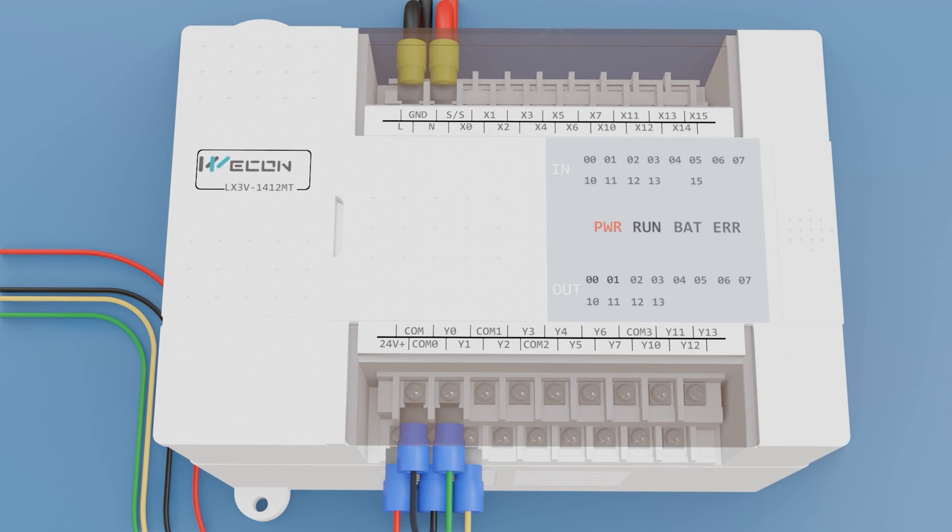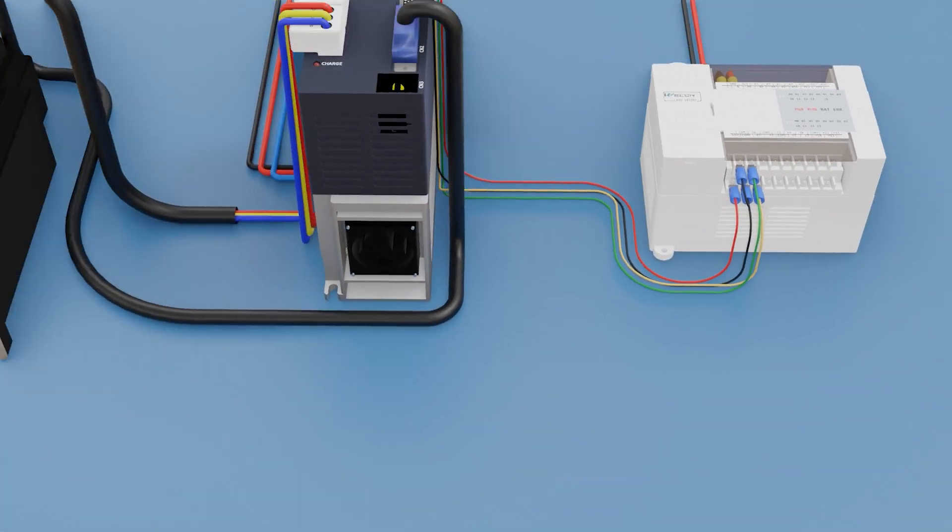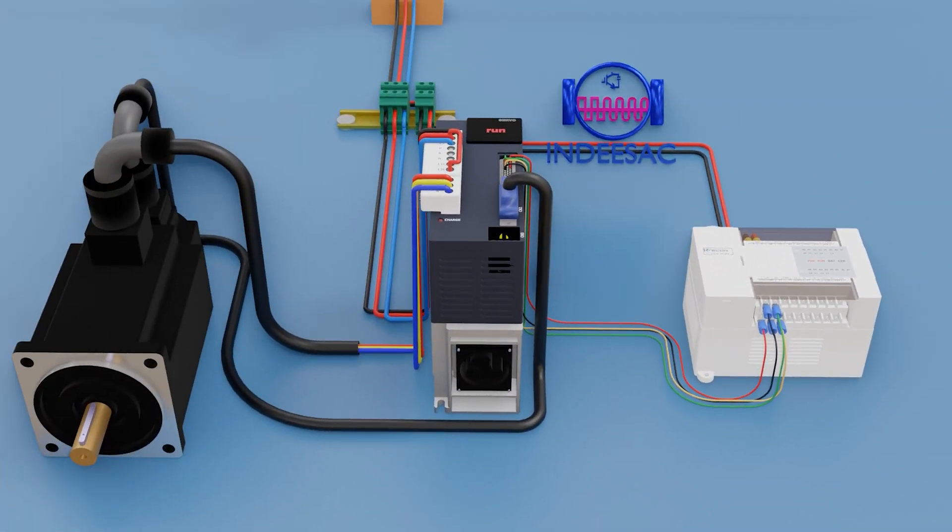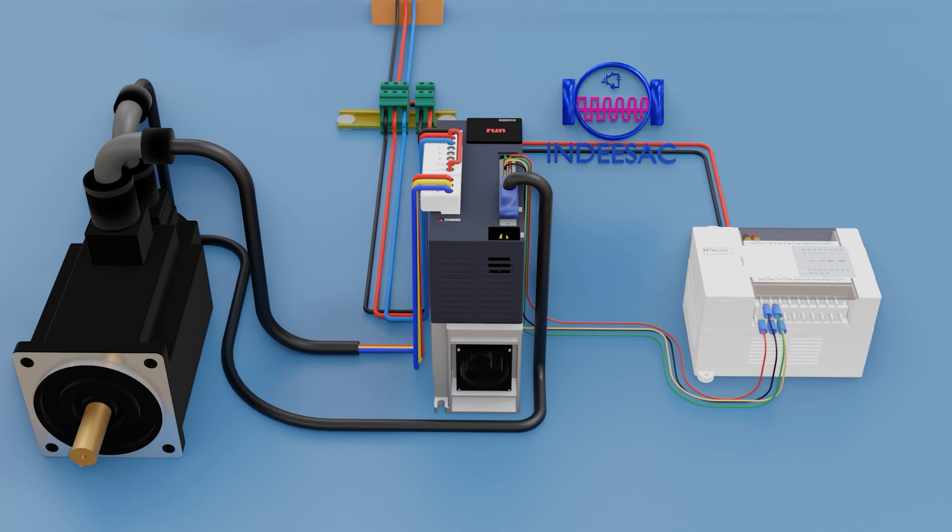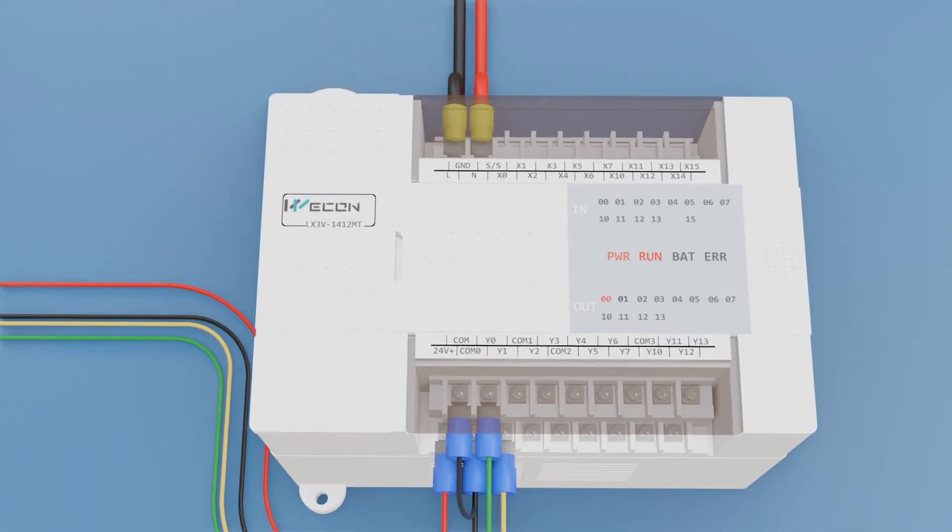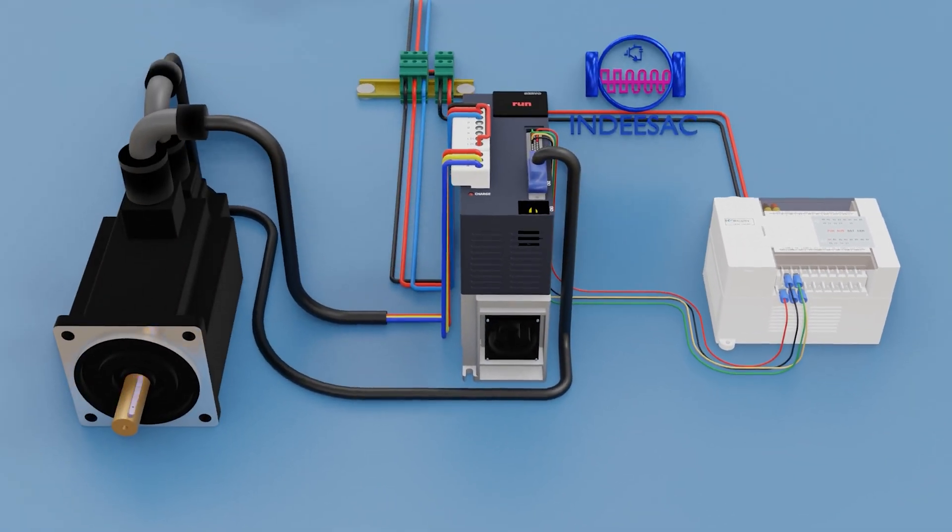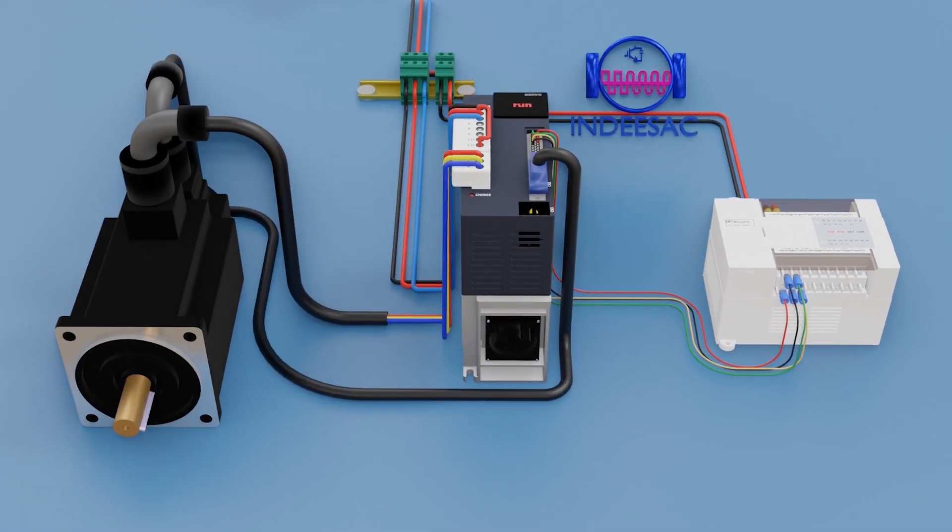Now we turn on the run state of the PLC with the programming already done. We test the servo motor in speed mode. As you can see, the PLC is on, only the Y0 output is turning to the right. We increase its speed.